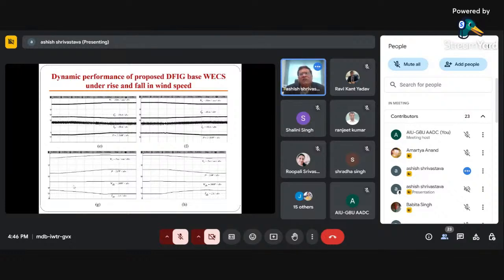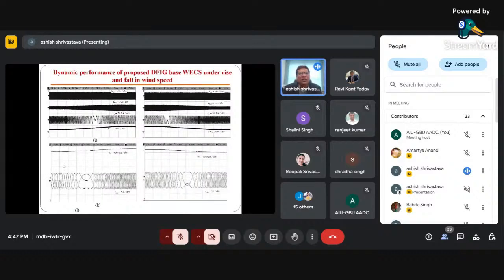So as you can see, whenever we are injecting or rejecting the load, small changes happen, but after that it will stabilize to the same voltage. Whenever a change has occurred, that change will be reflected in the waveform, but then the controller has to work immediately in a small time, and then it will stabilize again. How fast it will stabilize is decided by your controller.